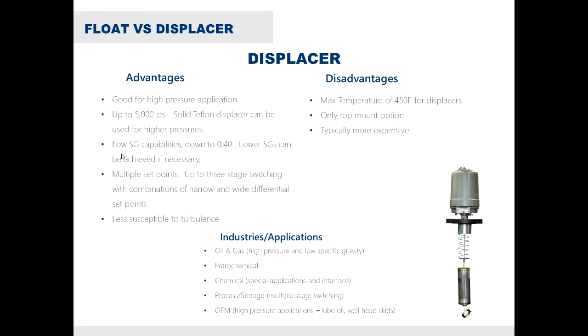Displacers now. The advantages for a displacer are quite the opposite when it comes to pressures and temperatures. Displacers are very good for high-pressure applications — they can easily do upwards of 5,000 PSI. The reason is you don't really have to worry about the weight of the displacer. You can beef that displacer up to handle 5,000 PSI without worrying about weight, because you can counterbalance that weight with the spring.